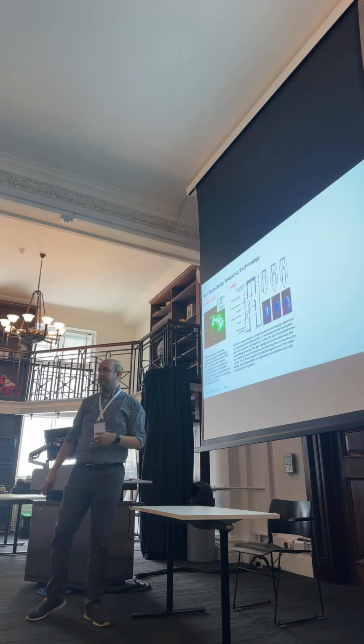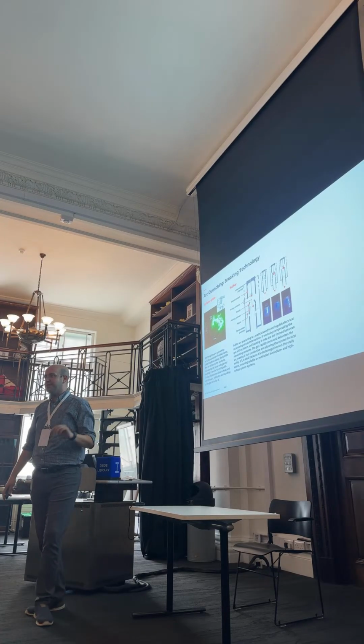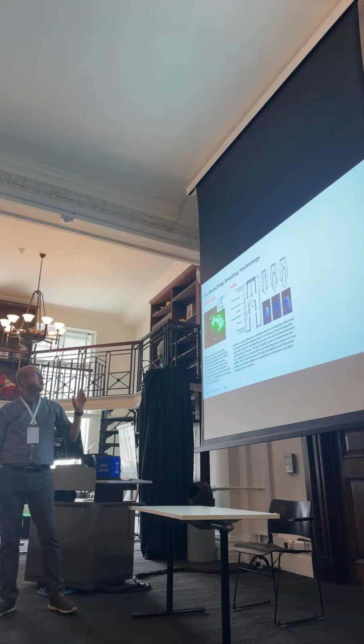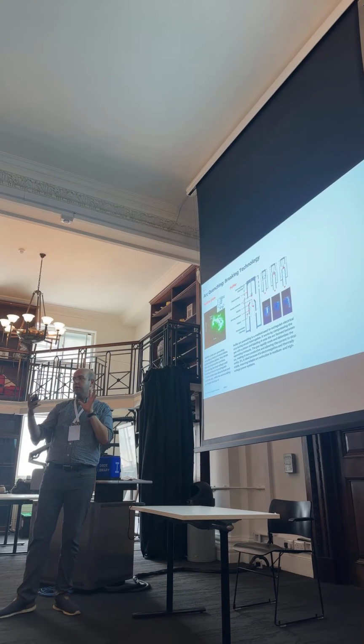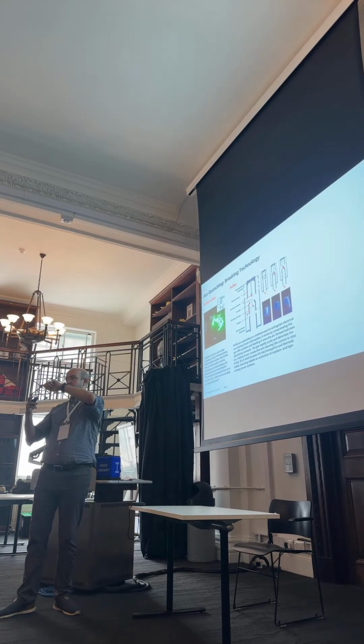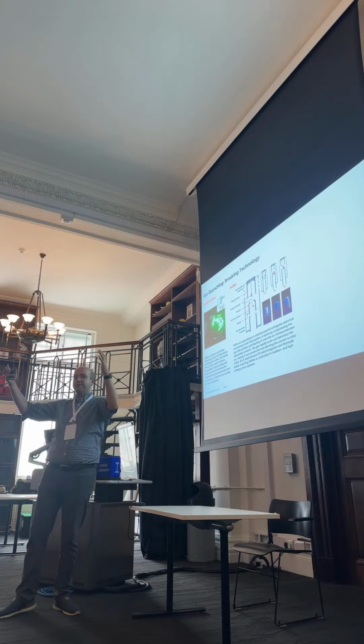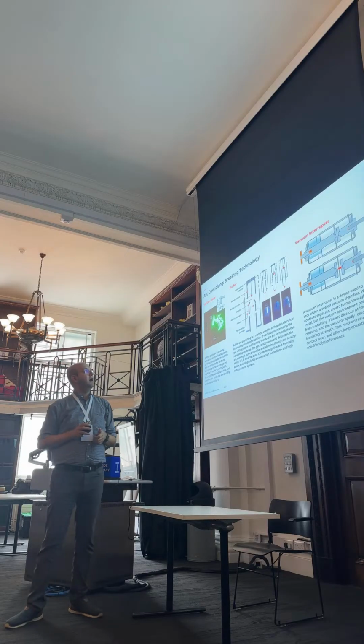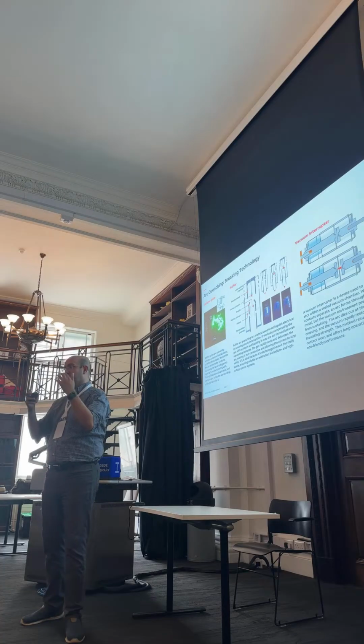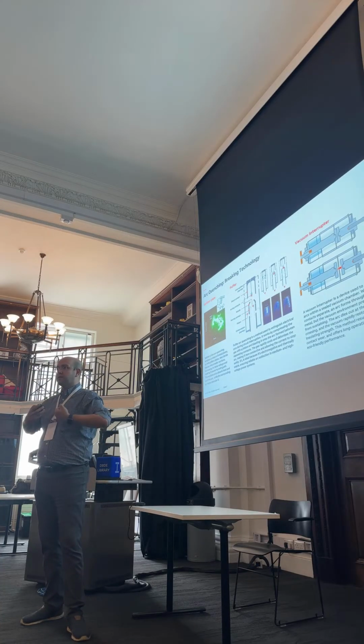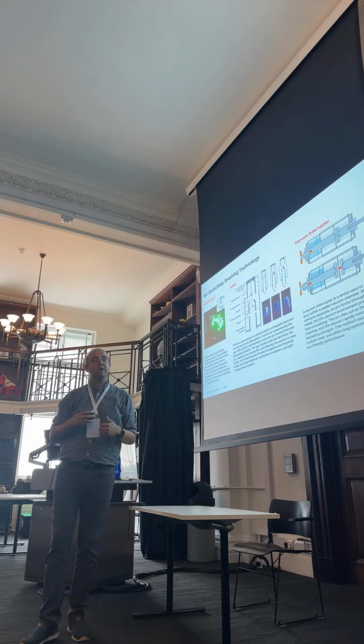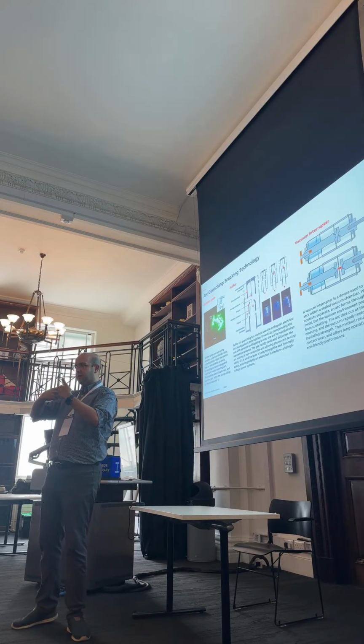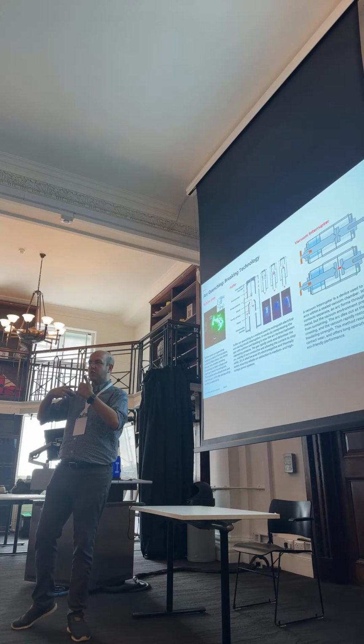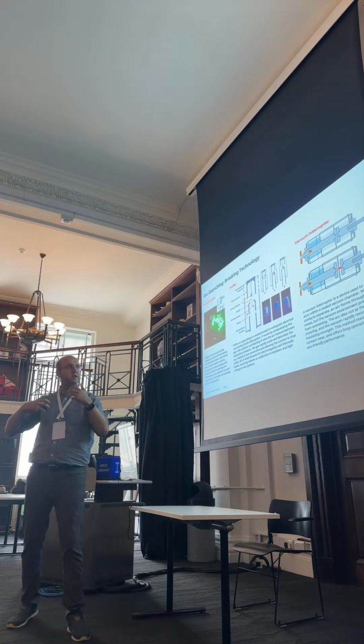The second one is puffer based. It's patented by ABB, a method used mainly by ABB, where, while making the contact, you create a cylinder that pushes air to the arc. So by puffing into the arc, you elongate the arc and cause it to break. And the third one, and the most common one used in higher safety devices, is a vacuum interrupter. So basically, at the point of contact, you create a vacuum bottle. And it's an ultra high vacuum. So it means there is almost no molecules between the two contacts. And as a result, by just slightly separating the contacts from each other, there is no chance that electrons can jump from the anode to the cathode. So that's another method.